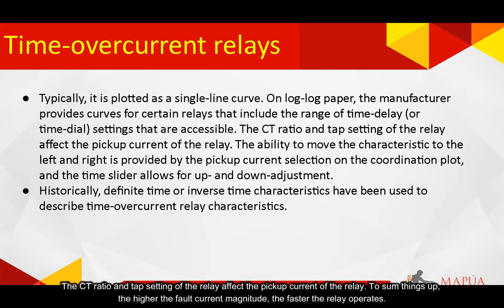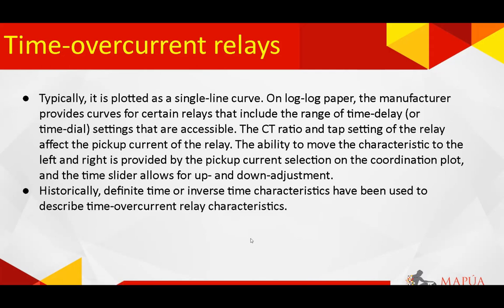The CT ratio and tap setting of the relay affect the pickup current of the relay. To sum things up, the higher the fault current magnitude, the faster the relay operates.